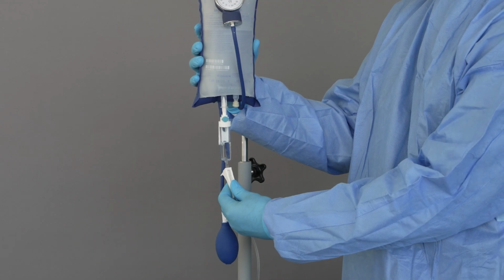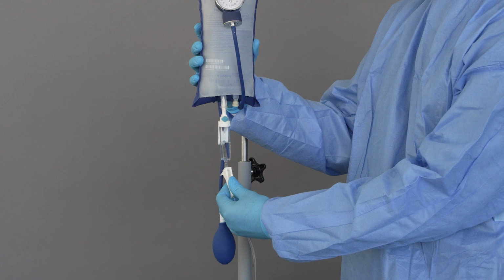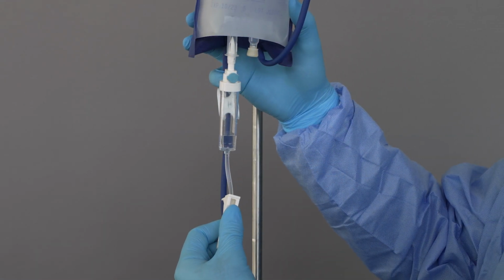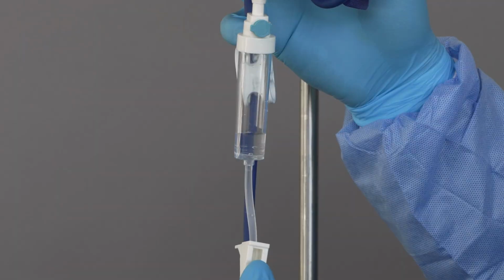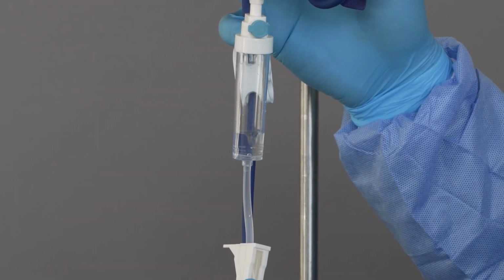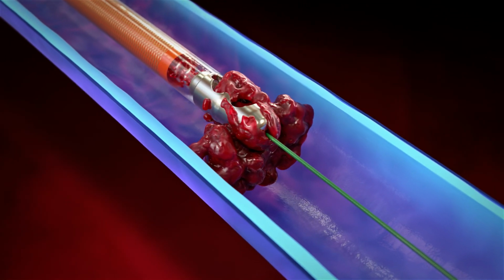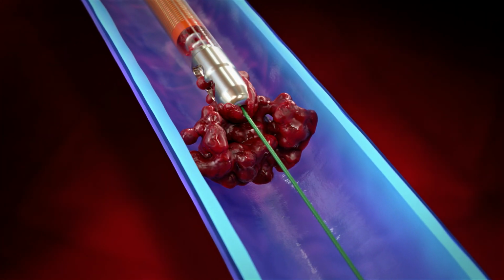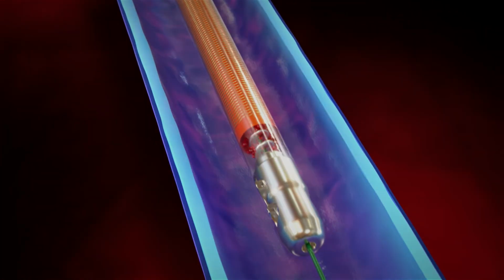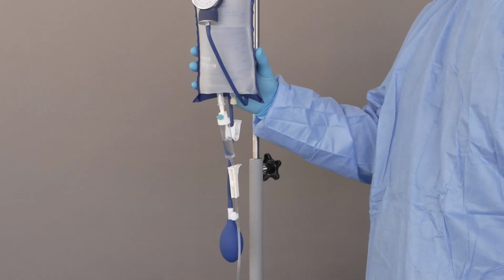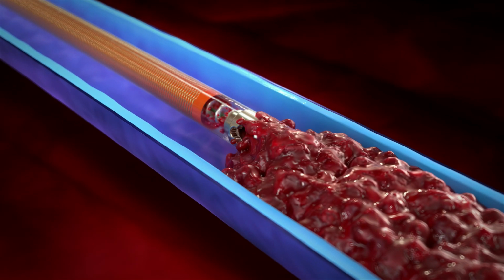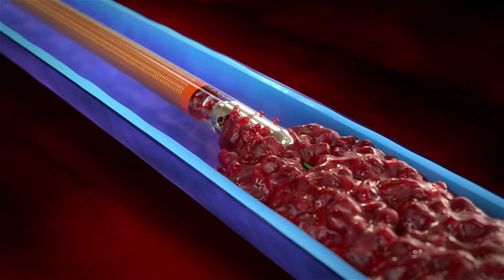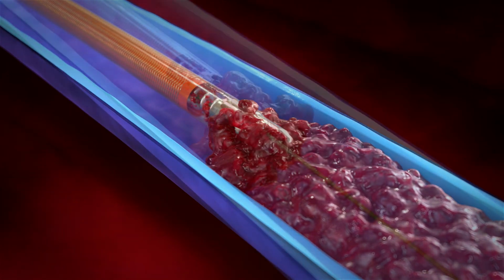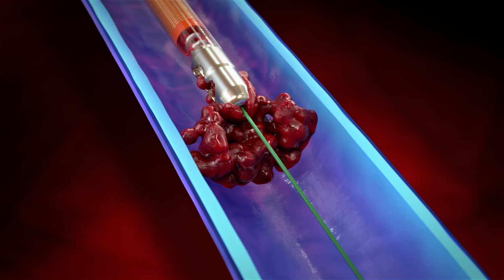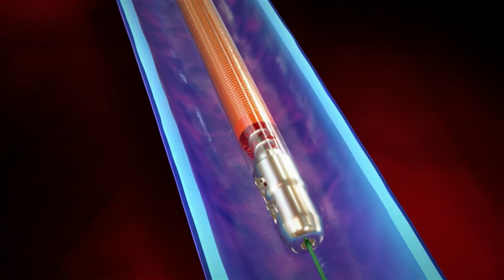Step 3. Starting infusion. Immediately before the continuous running of the Aspirex thrombectomy system, open the infusion line with the roller clamp. The flow to the drop chamber in the IV set should initially be fast dropping. Once aspiration is completed, and the Aspirex thrombectomy catheter is returned to the original starting position and deactivated, the infusion mix may be stopped. Note, the infusion mix will not have systemic effects as it will be immediately aspirated by the Aspirex catheter during procedure. This infusion mix allows for real-time feedback of vein filling and effectiveness of the treatment.